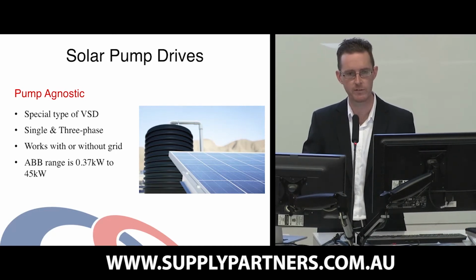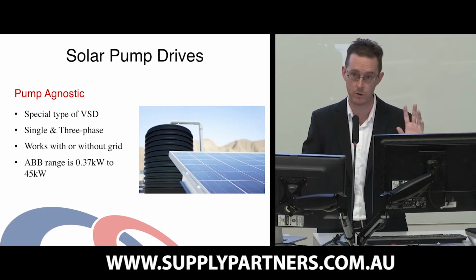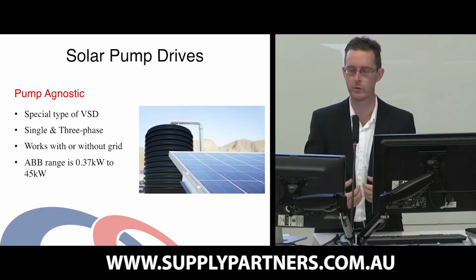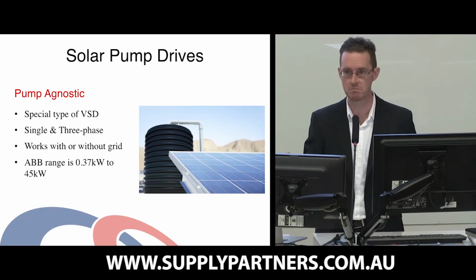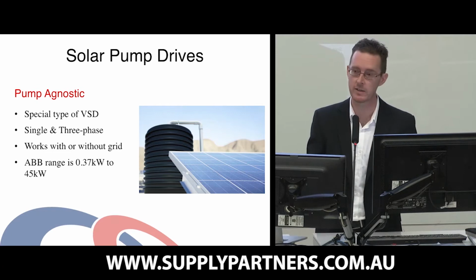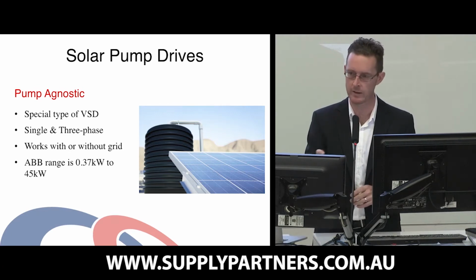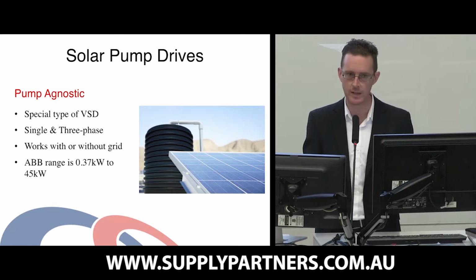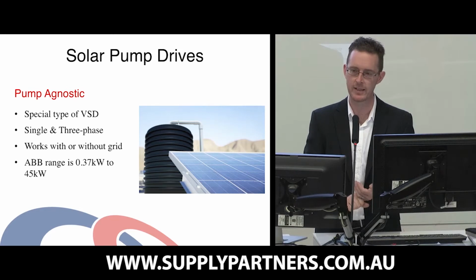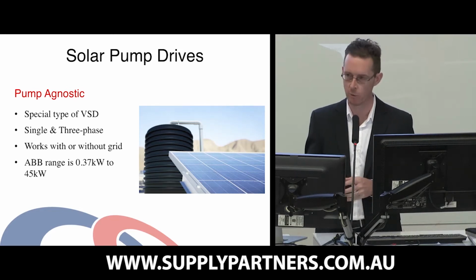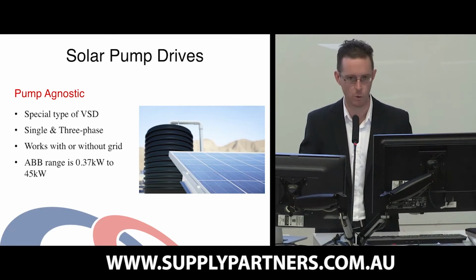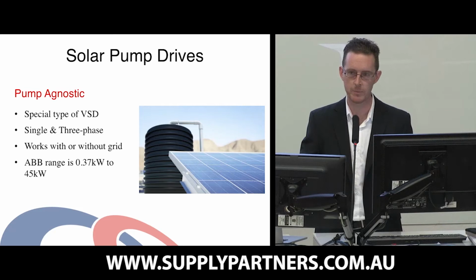And so if you have a customer that says, I need to power a 10 kilowatt pump, and it's Grundfos. Well, from our point of view, it's like, oh, okay, it's Grundfos. That's interesting, but frankly, we don't care. We're not worried about what the brand is on the pump anymore. We're completely pump agnostic. You just tell us what the electrical requirements of the pump are, and then we can supply a drive and a PV array that will supply the energy required to run the pump. And what that means is that we can now do pumping systems effectively off-grid without the need for batteries.